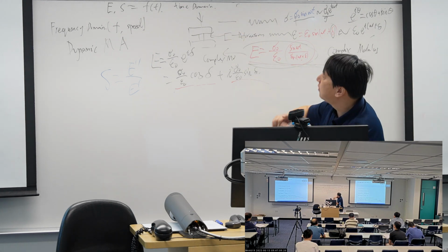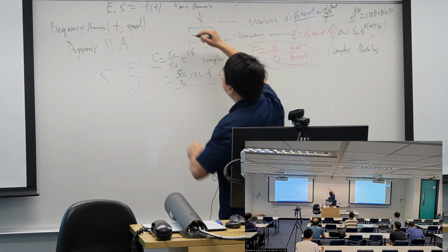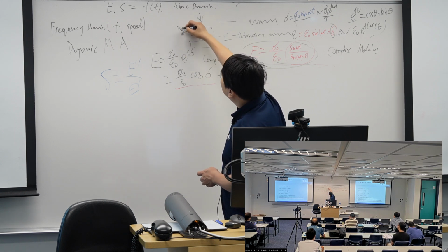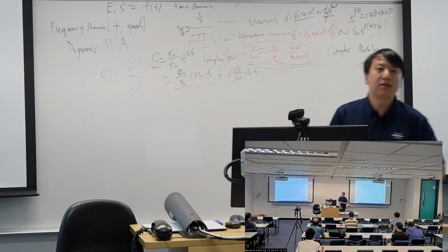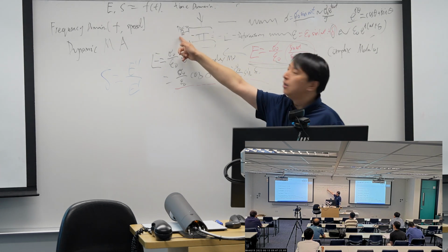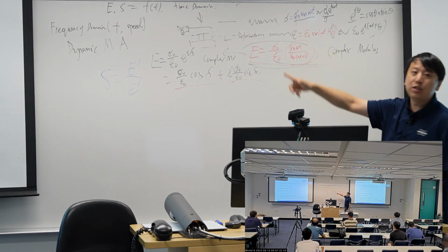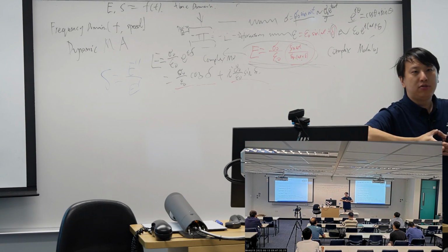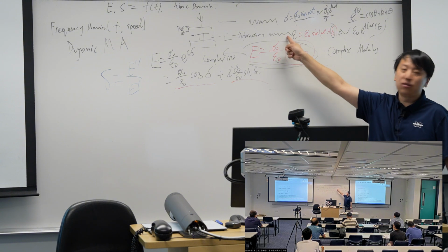They will place a position sensor here, so it knows the stylus is moving up and down, up and down, up and down. As such, it records the deformation. So our stylus measures the force, the position sensor measures the deformation, and we define the section area and the height.